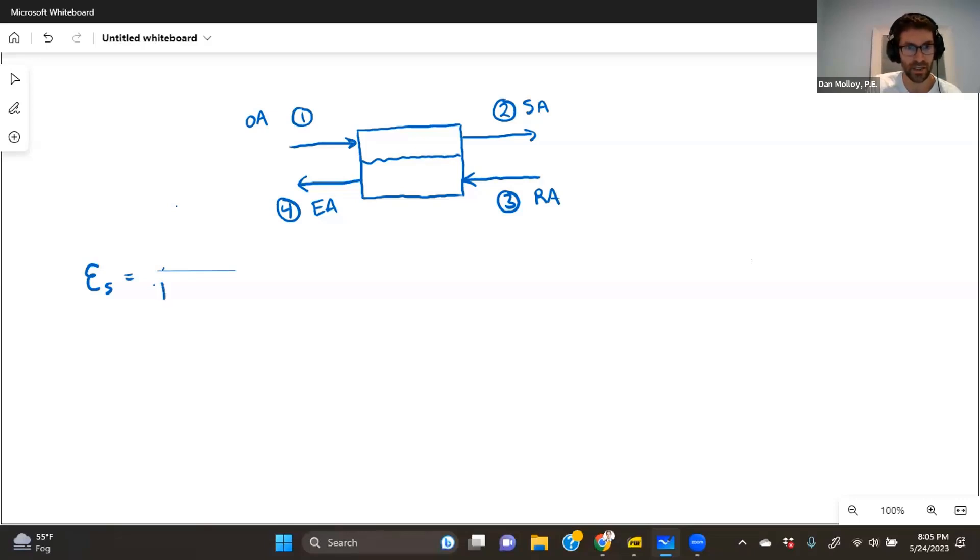So we could call that T3 minus T1. And then our numerator is what we actually get. What is the actual amount of heating that happens? We go from one to two. So we get some heating, but we probably don't get so much as to say we're going all the way to T3. So that'd be something like T2 minus T1, which is going to be less. And, you know, the largest this can ever be is 100%, but in most practical cases, it's going to be less than 100%. So that's the sensible effectiveness.